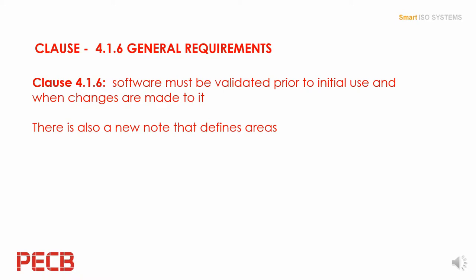Sometimes organizations don't even know where to begin with software validation, what to validate and how to validate it. Under those revisions, computer software can be used for, but is not limited to, product design, testing, production, labeling, distribution, inventory control, data management, complaint handling, equipment calibration and maintenance, and corrective and preventive action. If software involves or affects the quality management system, you need to validate. Plus, you need to have a very specific justification on how you validated that software, keeping records associated with what you did, and demonstrating that the software is doing what it's supposed to. This validation also applies when changes or updates are made to the software. There's a note. The note provides guidance on the areas that are involved in the validation process.